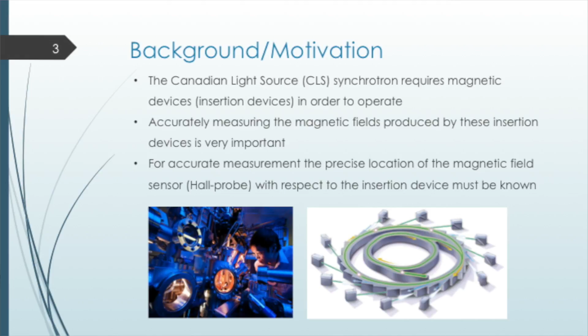And for accurate measurement of these magnetic fields, the precise location of the magnetic field sensor, in this case a Hall probe, with respect to this insertion device must be known. So what this is saying is that we want to know exactly where we're measuring the magnetic field. And this is very important because when they install these insertion devices into the synchrotron, if they're misaligned slightly, if we're measuring the magnetic field in the wrong location, it can actually take a lot of time to realign these.